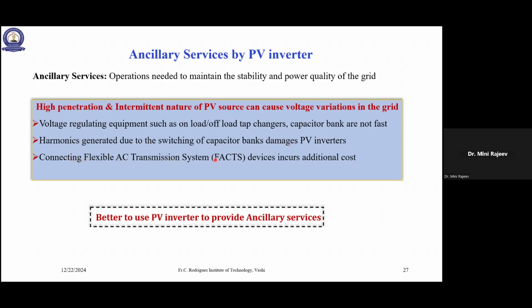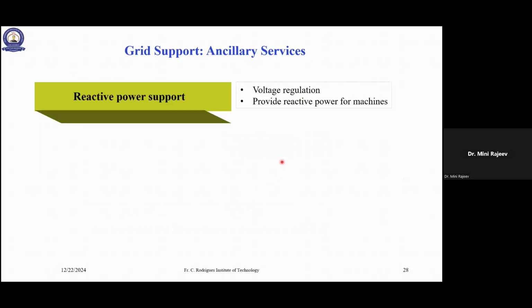Then connecting FACTS devices is also a solution, but it is an additional cost you have to incur. Instead of that, if the PV inverter itself can improve the stability and power quality of the grid, that is a good option. That is what I mean by ancillary services. I'm not going into detail, but I'll tell you what ancillary services a PV inverter can provide.